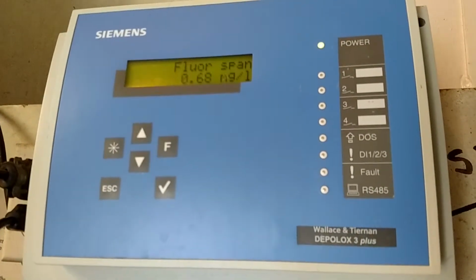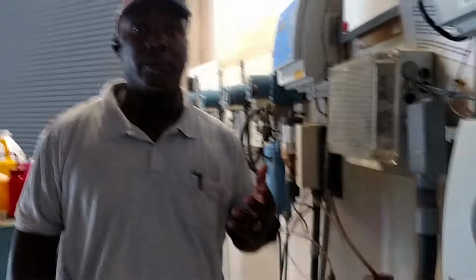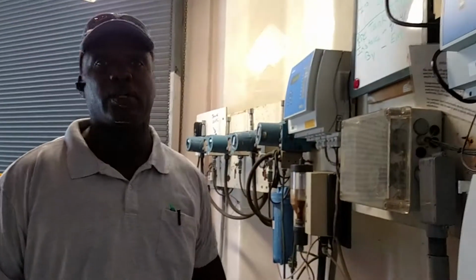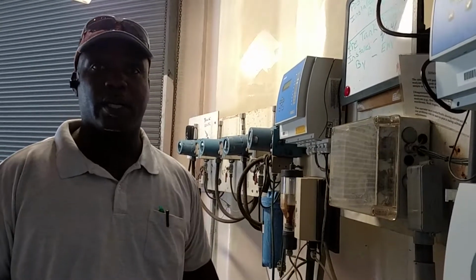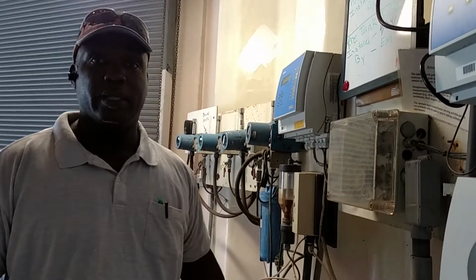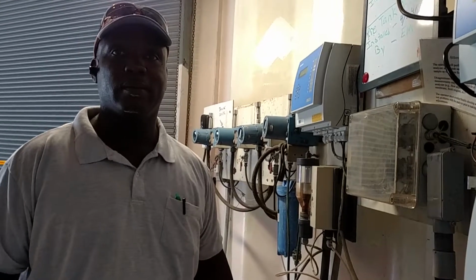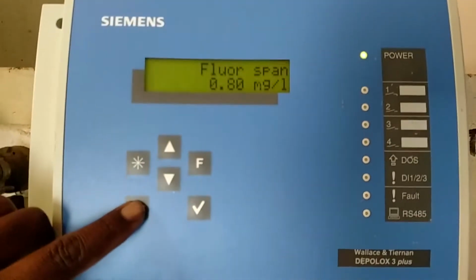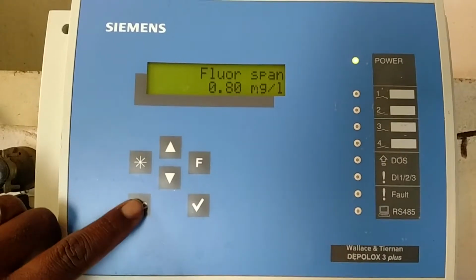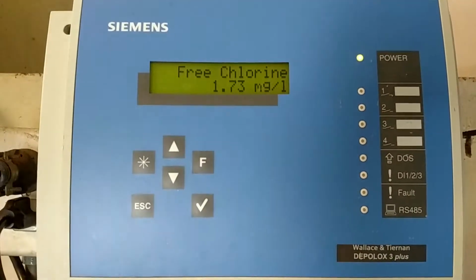Once that stabilizes, I can either hit escape twice to go back into the regular mode operation, or I can just leave it alone and then it will time out and go into the regular operation. And that basically will conclude the calibration. Okay, so it's done. No, it's in span. So you have to do what to put it back into regular? Hit check? Well, that basically is what it's reading after the calibration and back in the sample. So what I do is just hit the escape twice. Oh, you did just say that, didn't you?